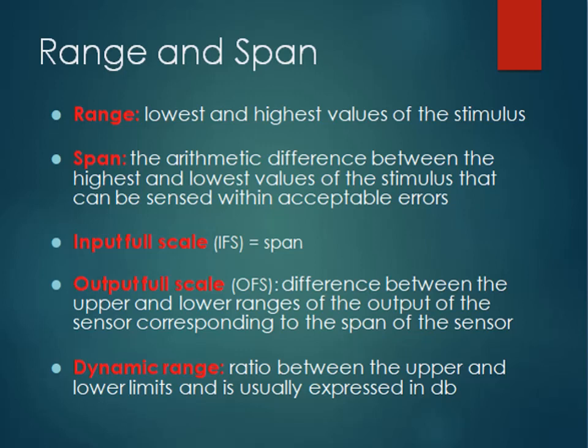Now let's take a look at range and span. So range is nothing but the lowest and highest values of the stimulus or quantity, and span is nothing but the arithmetic difference between the highest and lowest values of the stimulus that can be sensed within the acceptable errors. What is the input full scale? Generally input full scale is always equal to the span, and output full scale is the difference between the upper and lower ranges of the output of the sensor corresponding to the span of the sensor. Now we will talk about the dynamic range. So dynamic range is basically a ratio between the upper and lower limits and is usually expressed in dB.